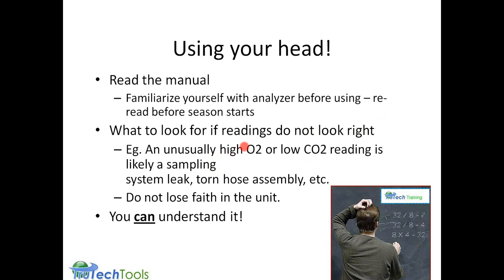But if you have an unusually high O2 reading that just doesn't make sense, or a very low carbon dioxide reading that doesn't make sense, it's probably a sampling leak. You've left the water trap open. You've left perhaps the filter in the probe loose, where you're getting some oxygen in where it shouldn't be. So just kind of use your head, know what the analyzer is supposed to do, what it's supposed to calculate for you. Don't lose faith in it, and just have some self-confidence. You can understand it. You can break this apart and understand it.